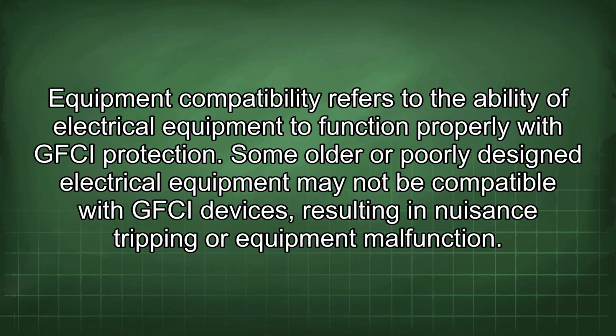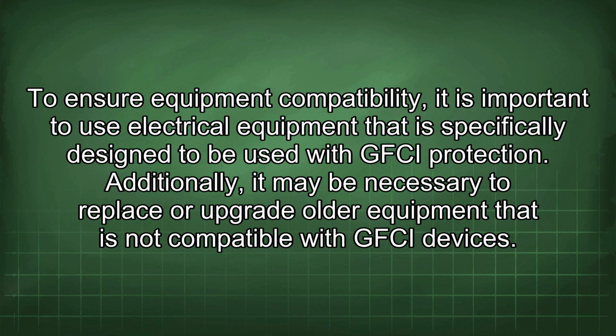Equipment compatibility refers to the ability of electrical equipment to function properly with GFCI protection. Some older or poorly designed electrical equipment may not be compatible with GFCI devices, resulting in nuisance tripping or equipment malfunction. To ensure equipment compatibility, it is important to use electrical equipment that is specifically designed to be used with GFCI protection. Additionally, it may be necessary to replace or upgrade older equipment that is not compatible with GFCI devices.